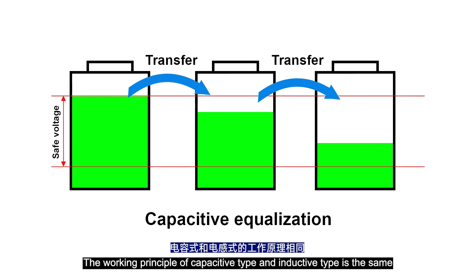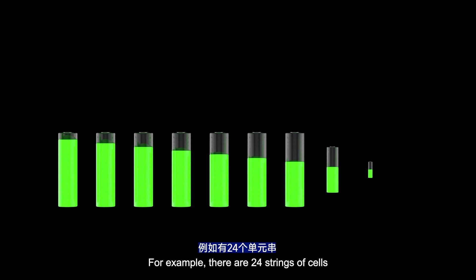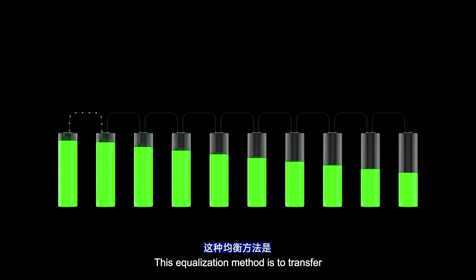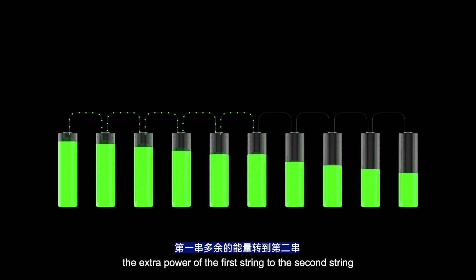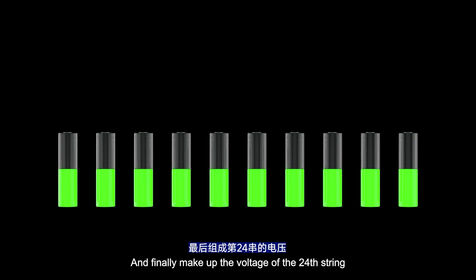The working principle of the capacitive type and inductive type are the same. For example, there are 24 strings of cells. The voltage of the first string is high and the 24th string is low. This equalization method transfers the extra power of the first string to the second string, then the second string to the third string, and so on, finally making up the voltage of the 24th string.